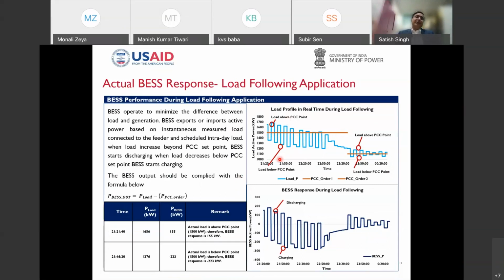This is much more important when we are trying to give a schedule from the utility perspective. If I'm giving a fixed schedule for different hours, for example, for one hour I'm saying I'll be providing 1500 or drawing 1500 from you from the load point. Similarly, in other time periods, I'll be drawing only 1100 from the grid, importing or exporting, both ways it works. The battery has to maintain the set point by charging or discharging. For example, if actual load is above the PCC point of 1500 kilowatt, the battery is responding by 155 so as to make the total sum equal to 1500, and similarly it does so in the other hours as well.